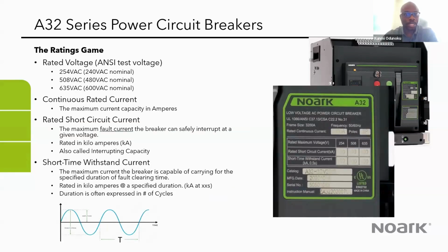Also, I want to talk about the ratings itself. So we have the rated voltage and we have the nominal voltage. Basically, the rated voltage is the upper limit of reliability for any circuit breaker. Typically, for the breaker to work very well, the rated voltage will take the upper limit value versus the nominal voltage. So for the breakers that we have, the A32 series, the voltage goes up to 600 volts nominal, and we have another series, the A40 series, where the voltage goes up to 800 volts. We will see in a little bit the specifications for these two types of breaker.